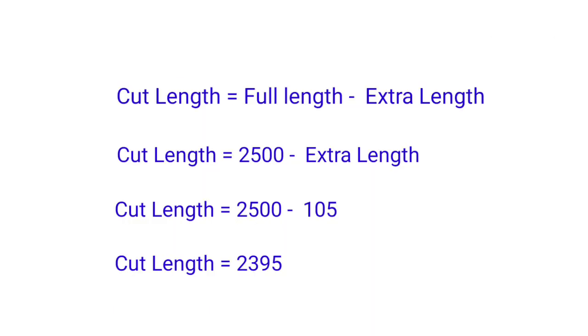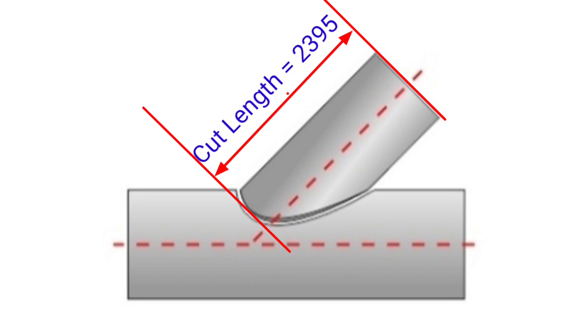Now we come to our final formula. Cut length equals full length minus extra length. Full length value, as per drawing, is 2500mm, minus extra length, which we solved as 105mm. So 2500 minus 105 equals 2395mm. That is the cut length value of pipe.